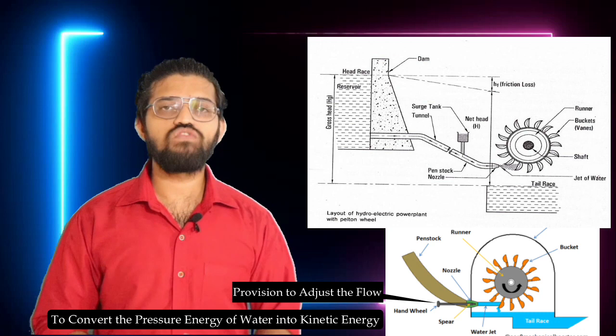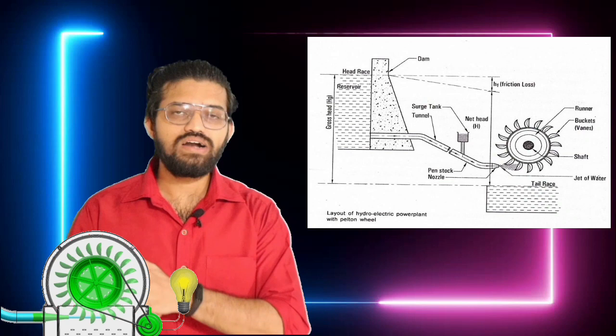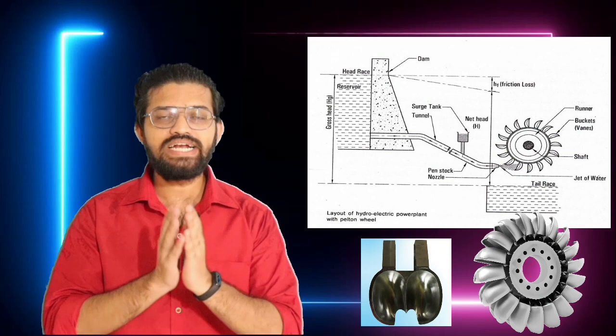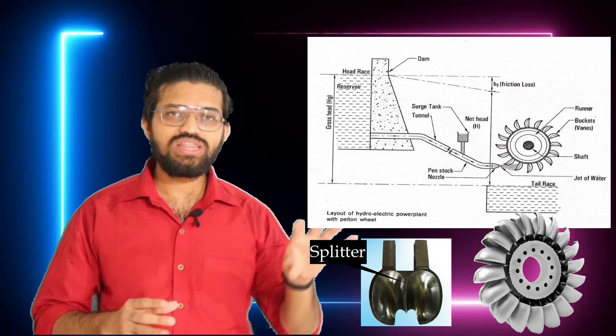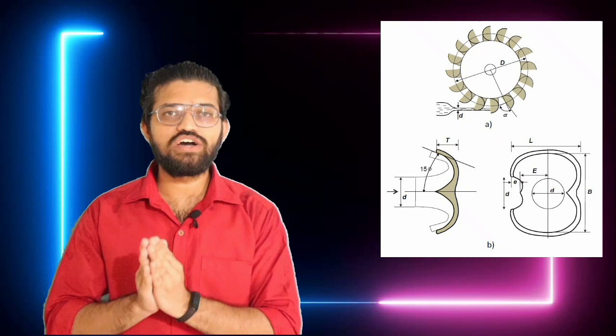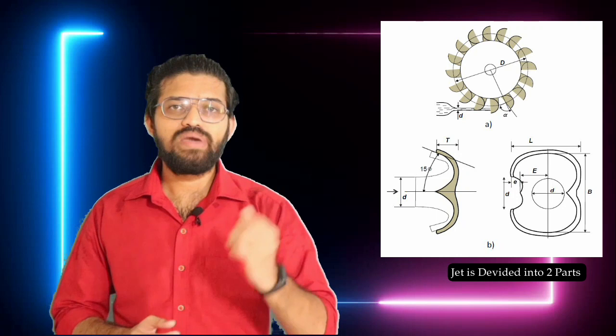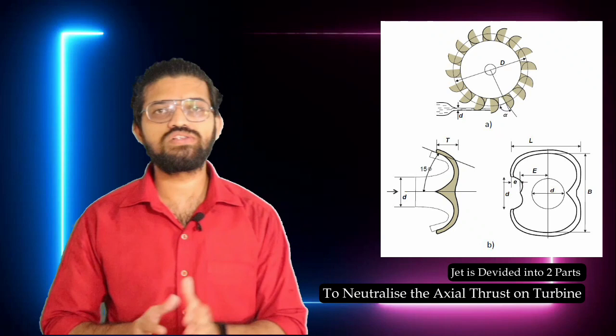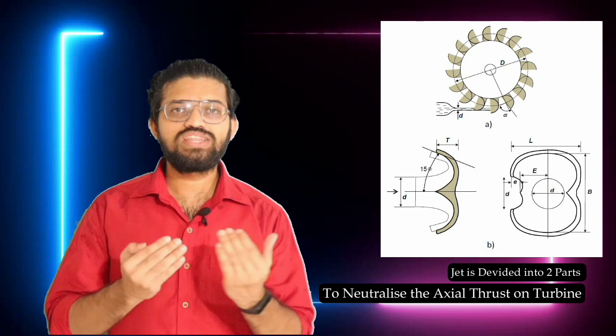The water coming out of the nozzle has higher velocity and higher kinetic energy. This jet strikes the Pelton wheel, which is a circular wheel having bucket-shaped blades. Each bucket consists of two hemispheres connected to each other with a splitter at the center. When the high-velocity jet strikes the bucket, the splitter divides the jet into two parts. The main function of the splitter is to reduce and neutralize the axial thrust produced by the striking jet.